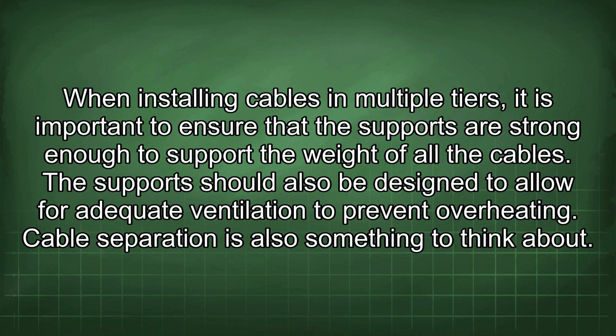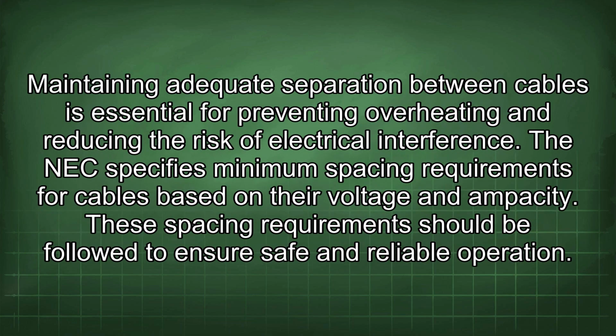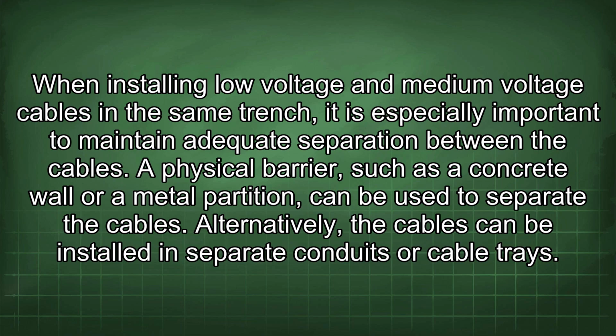Cable separation is also something to think about. Maintaining adequate separation between cables is essential for preventing overheating and reducing the risk of electrical interference. The NEC specifies minimum spacing requirements for cables based on their voltage and ampacity. These spacing requirements should be followed to ensure safe and reliable operation. When installing low voltage and medium voltage cables in the same trench, it is especially important to maintain adequate separation between the cables. A physical barrier, such as a concrete wall or a metal partition, can be used to separate the cables. Alternatively, the cables can be installed in separate conduits or cable trays.